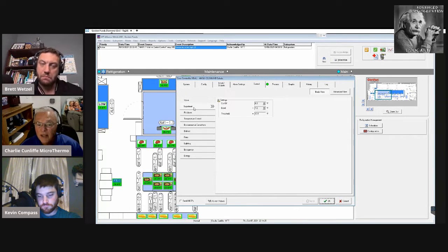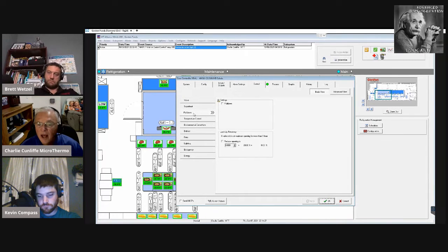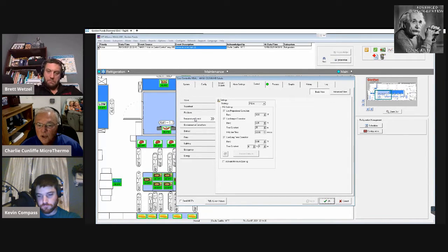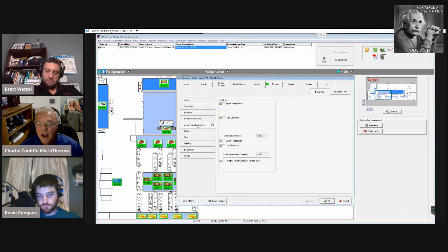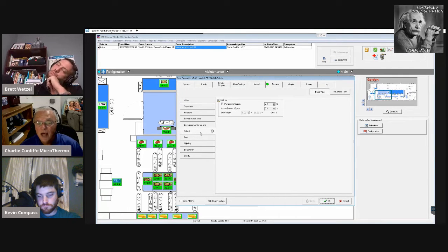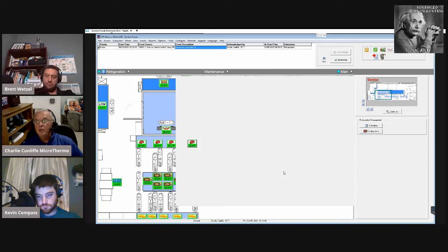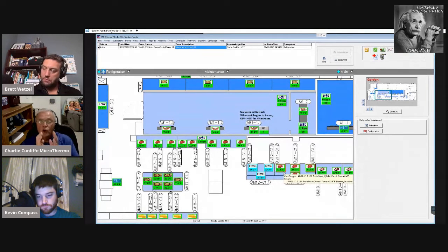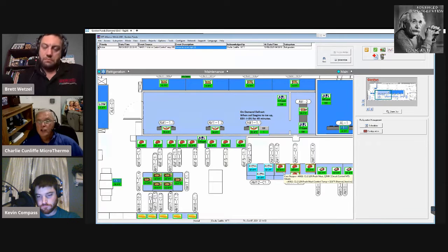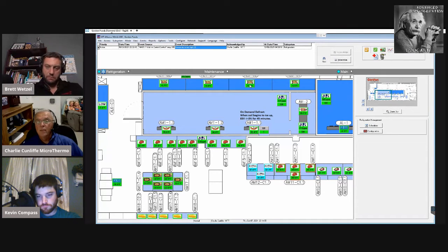Then there's a superheat algorithm, a pull down algorithm, a temperature control algorithm, an environmental correction - they're not using that because I think this could be a POS - and a defrost algorithm. So you have all of these algorithms set up, and that's how we get those case controllers to be so tight, because there are so many correction factors running concurrently in the control. That's why we're able to get graphs like this.